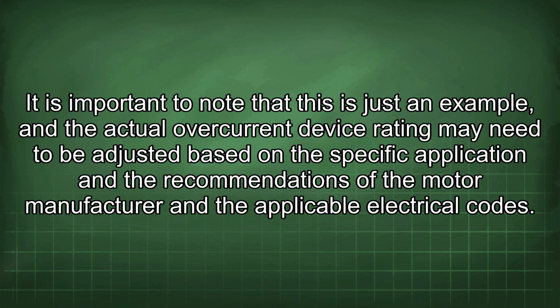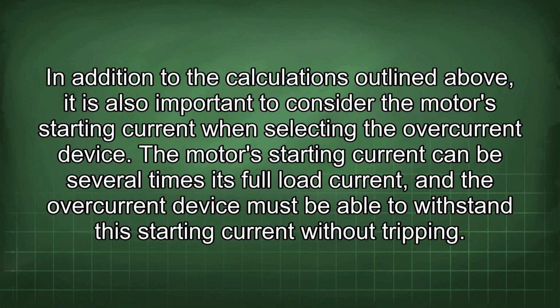It is important to note that this is just an example, and the actual overcurrent device rating may need to be adjusted based on the specific application and the recommendations of the motor manufacturer and the applicable electrical codes. In addition to the calculations outlined above, it is also important to consider the motor's starting current when selecting the overcurrent device. The motor's starting current can be several times its full load current, and the overcurrent device must be able to withstand the starting current without tripping.